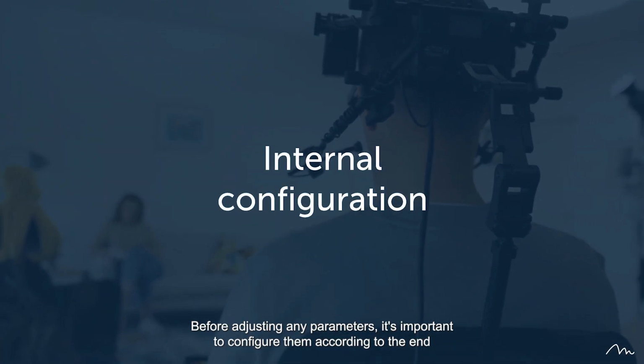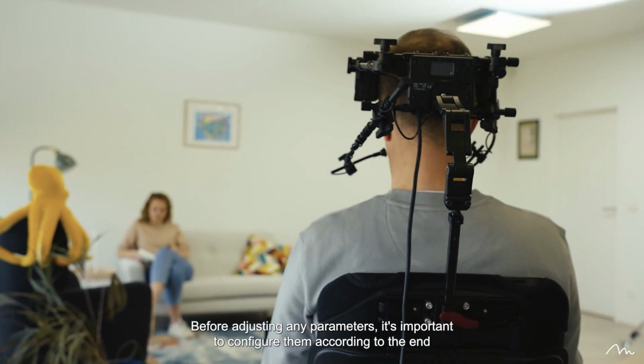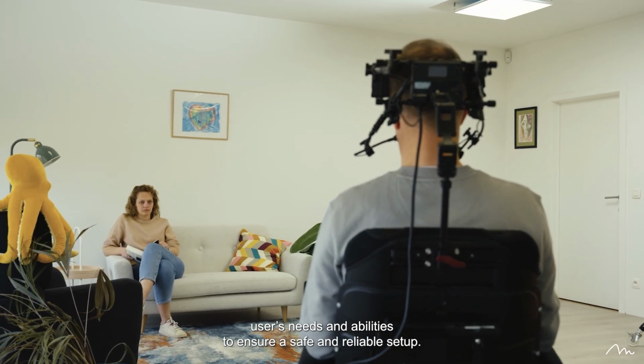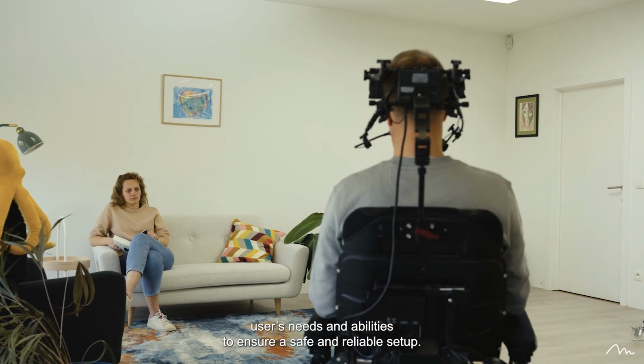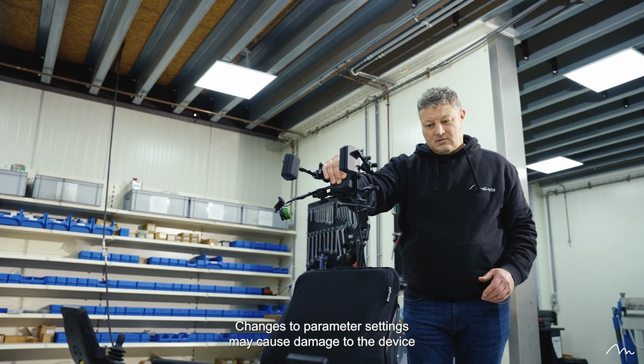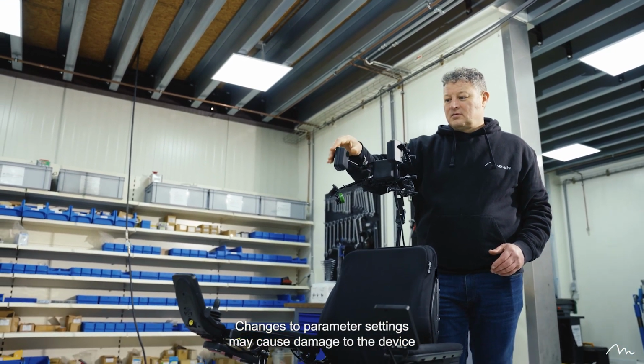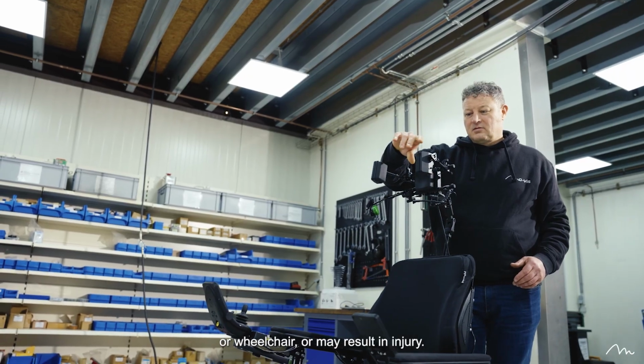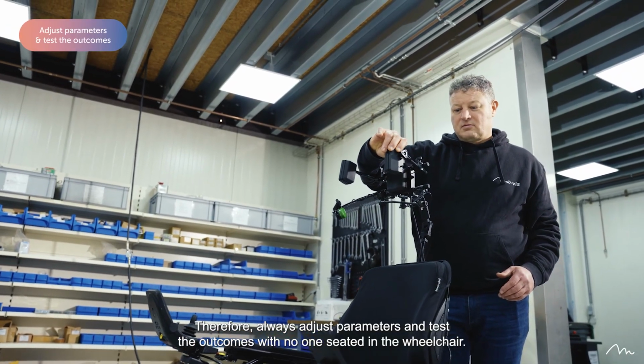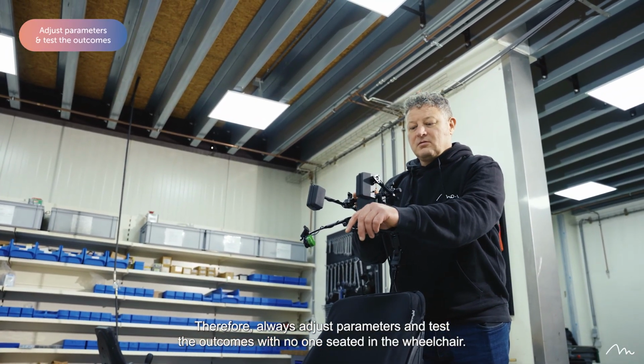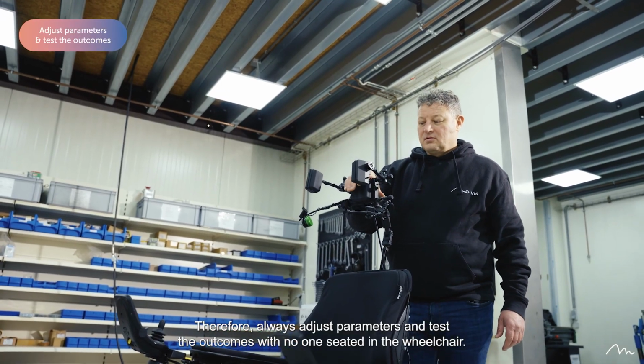Before adjusting any parameters, it's important to configure them according to the end user's needs and abilities to ensure a safe and reliable setup. Changes to parameter settings may cause damage to the device or wheelchair, or may result in injury. Therefore, always adjust parameters and test the outcomes with no one seated in the wheelchair.